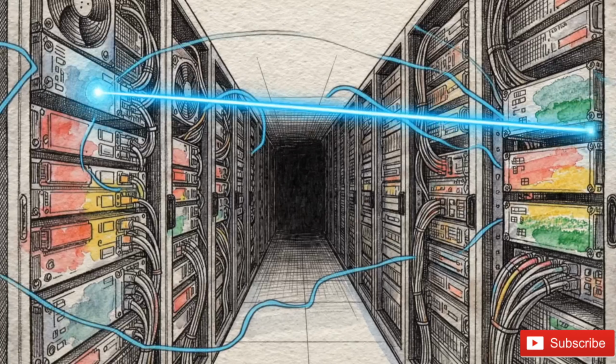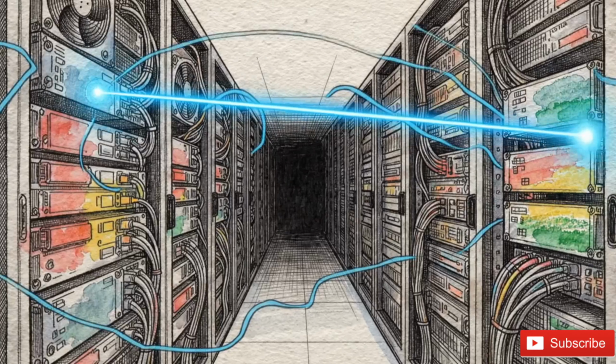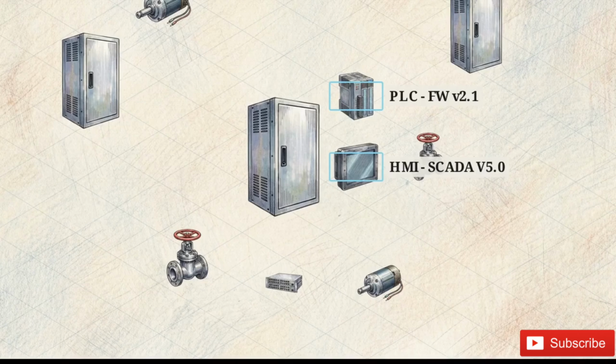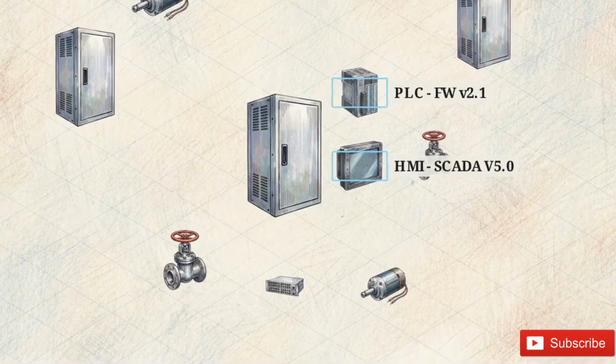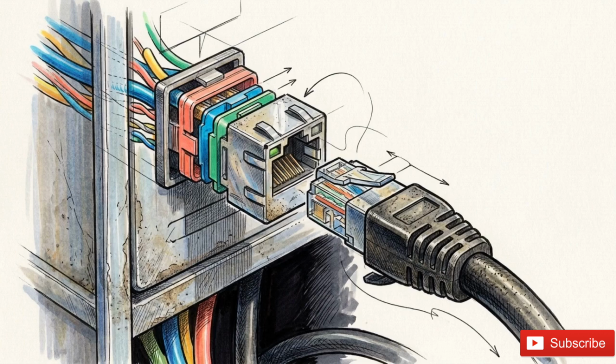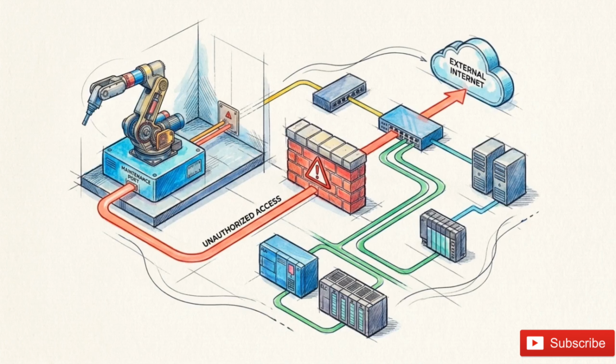Step 1 is conducting a comprehensive inventory and mapping of all OT assets. You cannot secure a facility without knowing exactly what is at risk. This catalog must include all hardware and software: PLCs, SCADA systems, HMI stations, and the specific firmware versions running on every device. The inventory must also capture infrastructural components like network switches, cabling, and external connections used for remote vendor maintenance. Omitting a single vendor access port provides an undocumented, unimpeded backdoor for attackers. One unmapped data port can render the entire security perimeter useless.